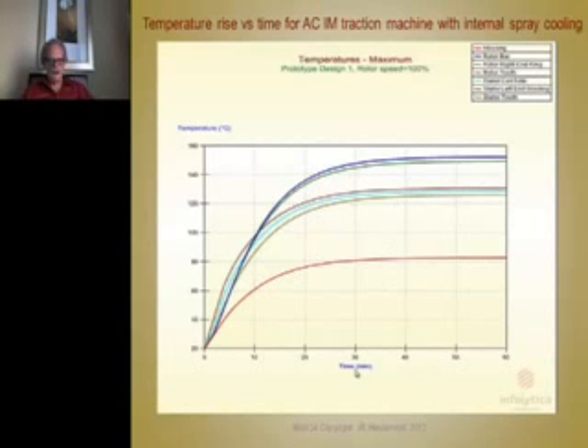And it took this thing about 30, 40 minutes to get up to temperature. Certainly, it stabilized after an hour. So for intermittent duty, you could work this motor a lot harder for 10 minutes or 5 minutes or something like that. I think that's clear from this. You could do these kind of models with some duty cycle and see it go up and down, as the temperatures of all these things will drop during the off times and then go back up. So you could study these temperature rise graphs, and each one of these color codes a different part of the motor. Now you see the housing is the coolest because that's the coolest part of the thing. The hottest are probably the end windings, I believe.